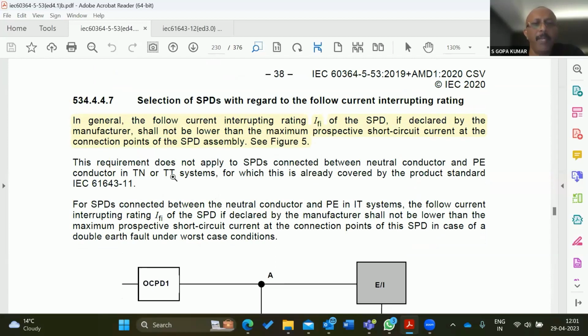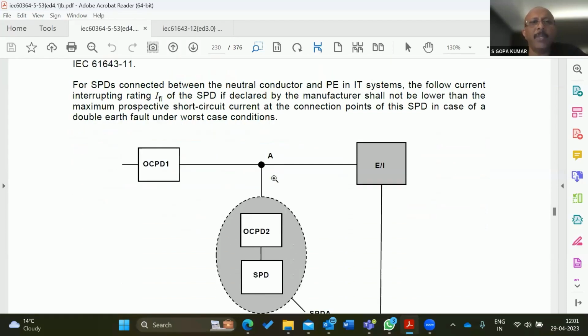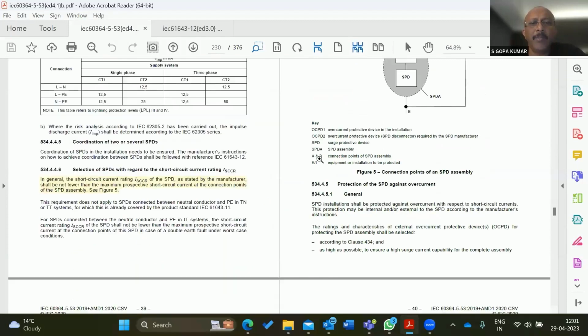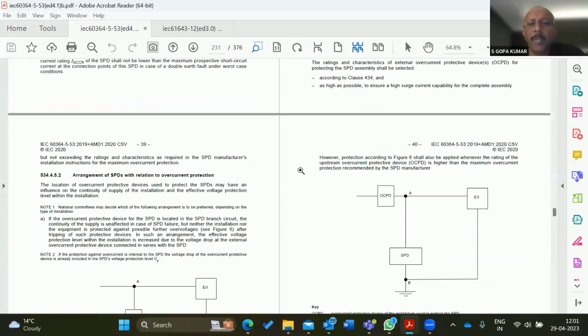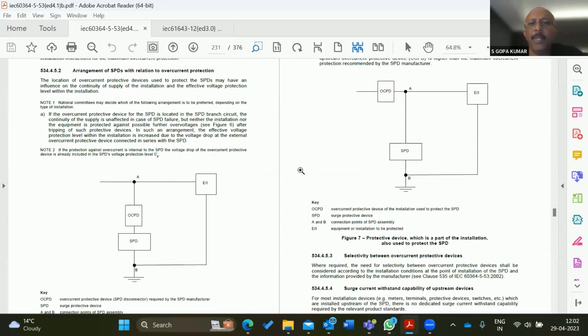But most often, when we tell the panel builder, please don't use it because this is compromising the quality of your panel, they end up saying that no, the consultant or the designer has included this SPD and it is an economical model, so we go for this. Most often, the users are not really taking care of such measures. The idea of showing these lines is to inform you that what is inside the SPD is sometimes just an MOV, which can be bought even from the market. But as an SPD assembly, a lot of safety features are included. So we are actually paying for the safety features which are inbuilt in the SPD.